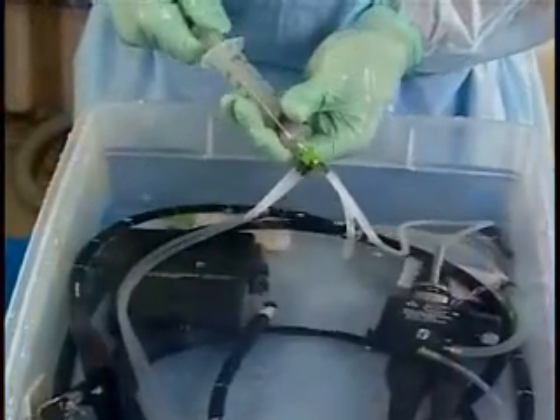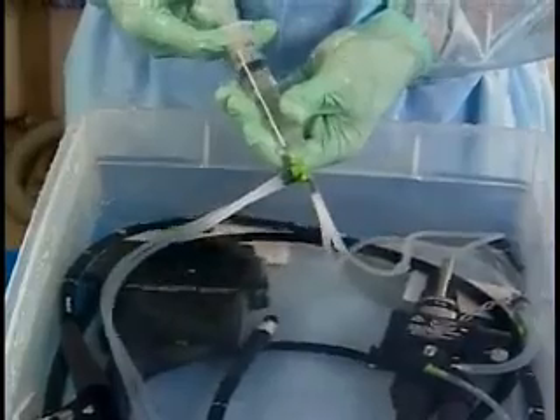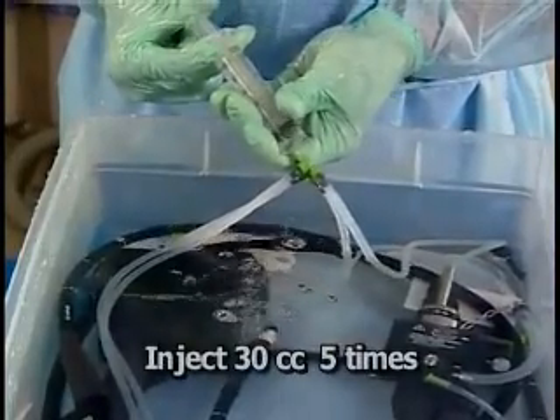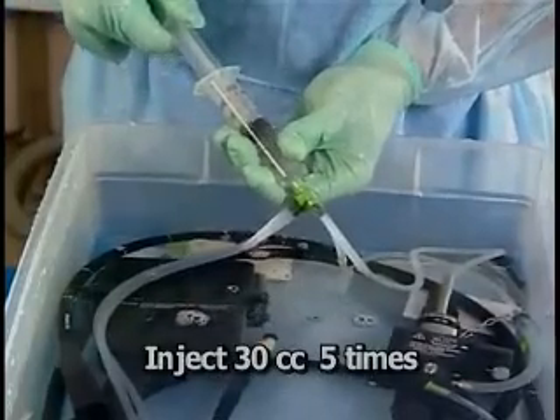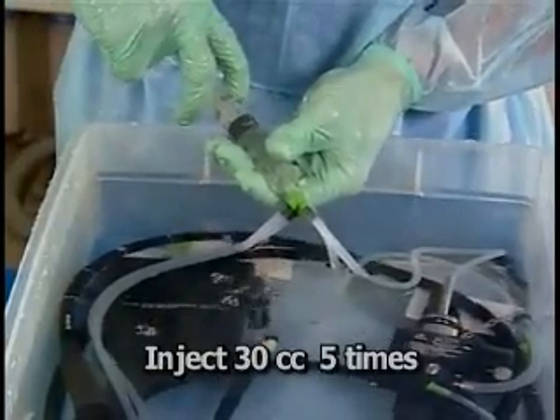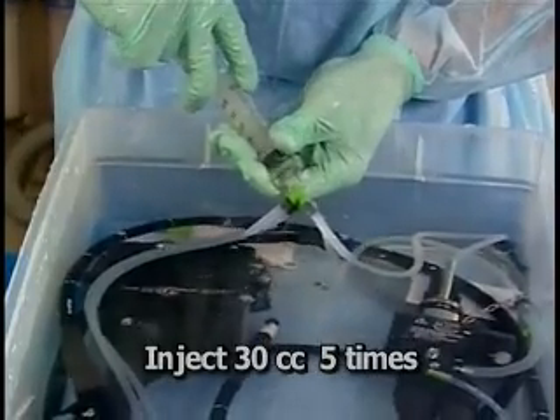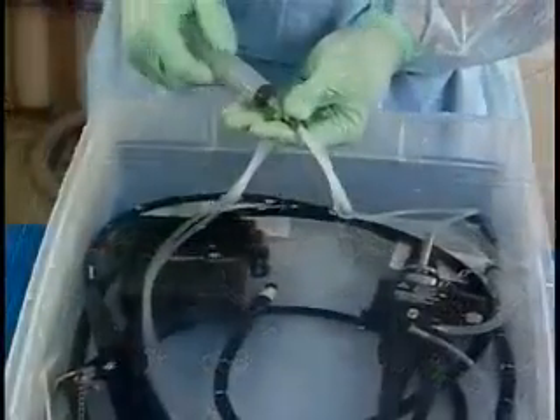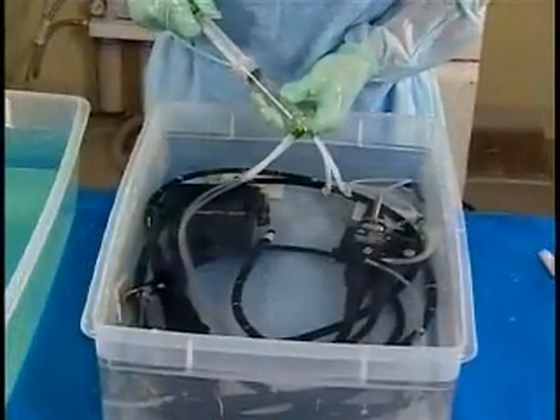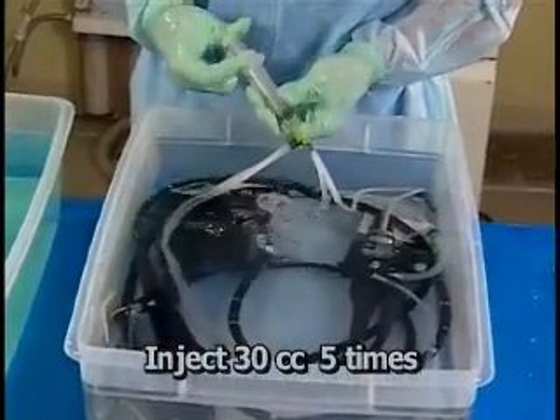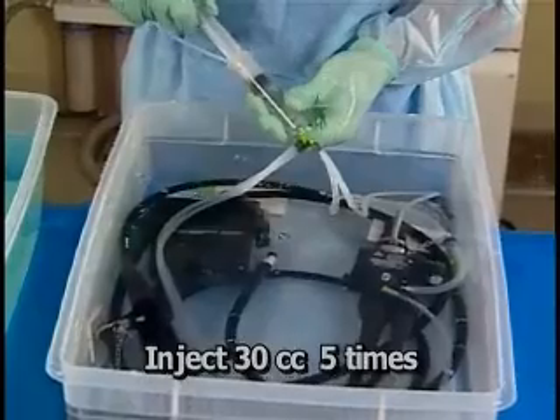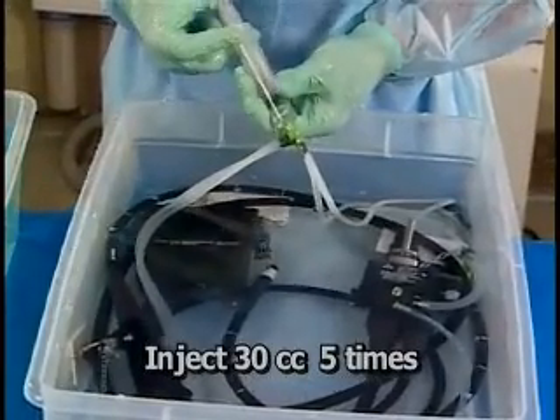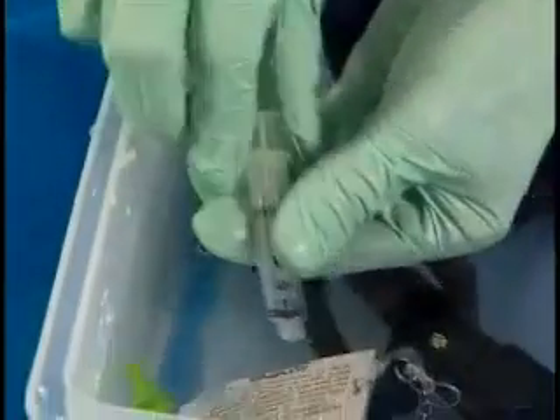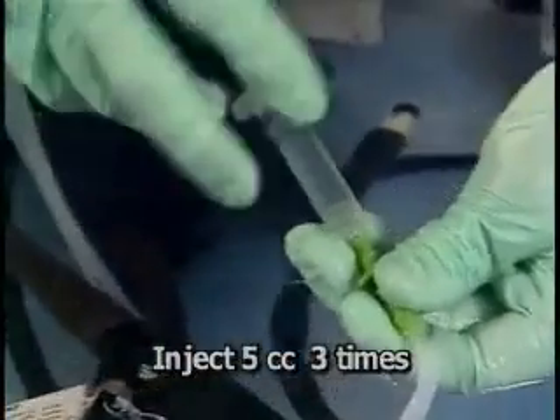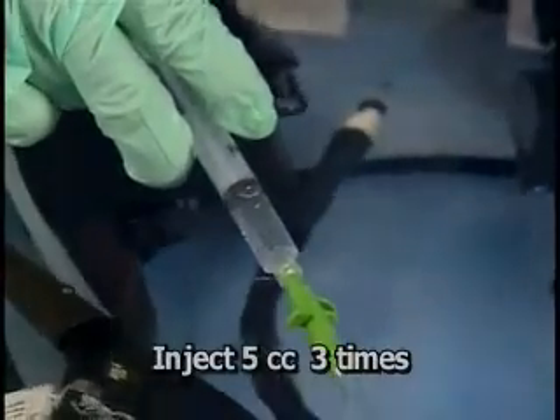Next, with the intake filter immersed in the rinse water, use the syringe to flush 150 cc's of rinse water through the air, water, and balloon channels. Move the syringe to the suction connector and do the same to rinse the suction channel. If you are reprocessing an endoscope with an elevator channel, inject 15 cc's of water into the elevator wire channel using a 5 cc syringe.